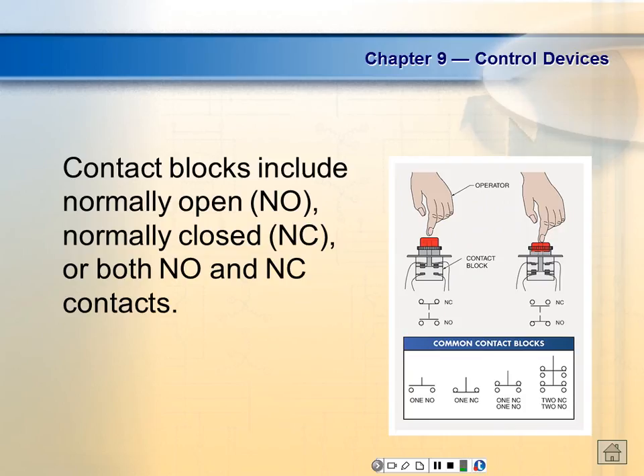Contact blocks include normally open, normally closed, or both normally open and normally closed contacts. A lot of them you run into in industry, just about all your push buttons are what we call double break, double make contacts. And what's the advantage of those? One side fuses shut. Yeah, one side welds and it rocks and will open up.